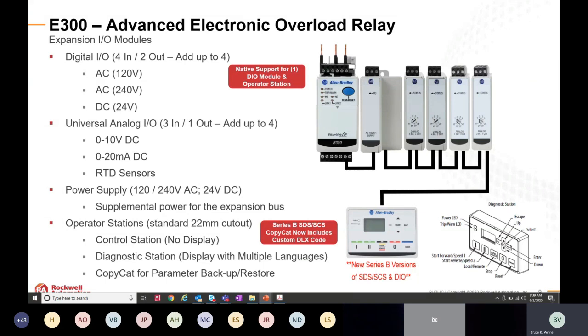So the other nice thing about the E300 with the diagnostic station or control station is that once you have the E300 configured, you can do what's called a copycat procedure. So through a series of a couple of different buttons within the device itself, we'll grab a snapshot of all the parameters of the E300 and store that right in that little handheld device. So that in the event the device requires replacement, you can simply write those parameters back to the device and you're off and running again.